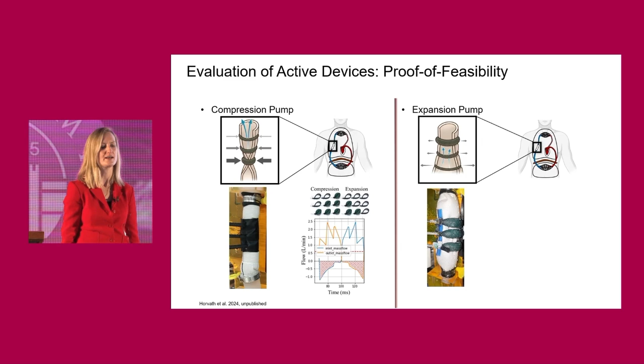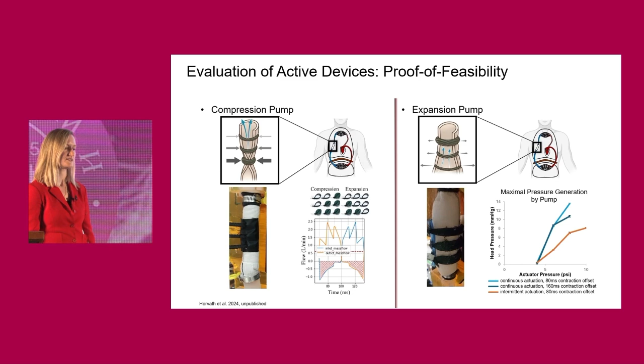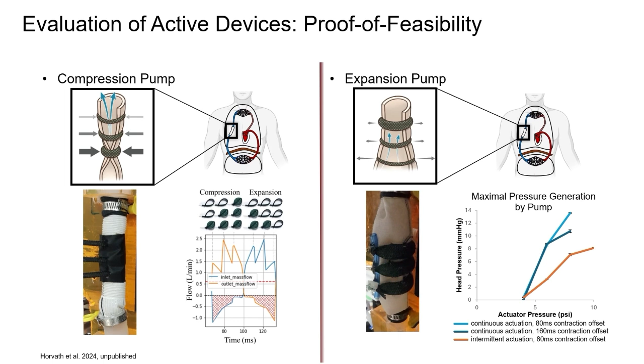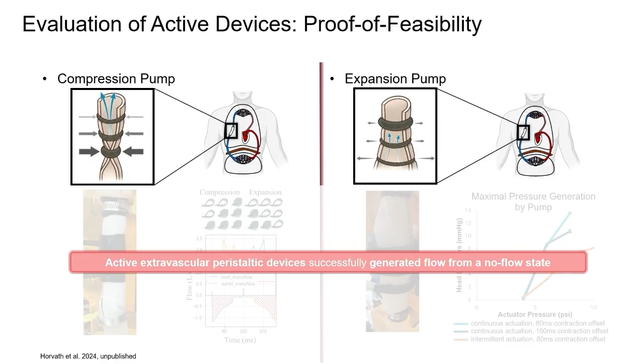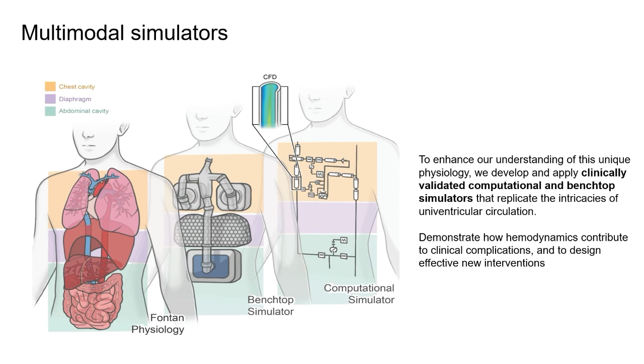We can evaluate these devices on the bench. Here's a compression pump on the left and an expansion pump on the right. We can actuate these in different ways, changing the sequence of actuation, the pressures, and how they work. This, again, is not an additional surgery. It's an active conduit instead of a passive one. With these, we were able to successfully generate flow from a no-flow state, which is promising. But we really needed to understand it better, and with our clinical partners, we saw there was a need to build better simulators of this condition.